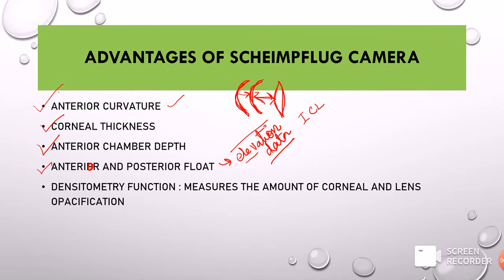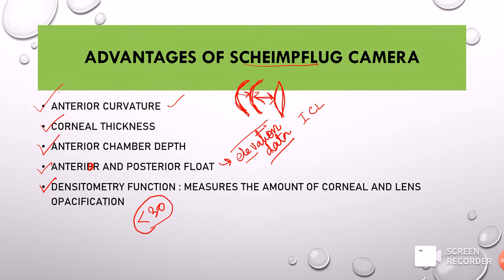The posterior curvature is very important because in conditions like early keratoconus, only the posterior part of the cornea is affected first. One more function specific to Scheimpflug technology is the densitometry function, which tells you about the density — and therefore the clarity — of the cornea and lens. The densitometry value should normally be less than 30, indicating a clear cornea. A value above 30 usually indicates corneal opacity.